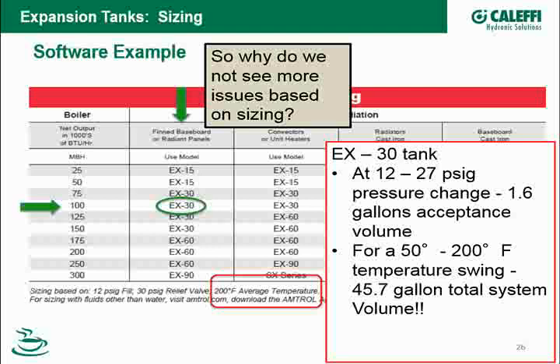And the other thing I would say to that, guys say, well, I'm not going to buy a big expensive bladder type of tank for that, and they try to use just plain steel compression tanks. Be aware that sizing can be 75, 80% bigger on a plain steel tank where you don't have a captive air bubble in there. So sometimes you do want to run the numbers if you're doing stuff out of the typical residential volume type of system. So that's where you have all the information.